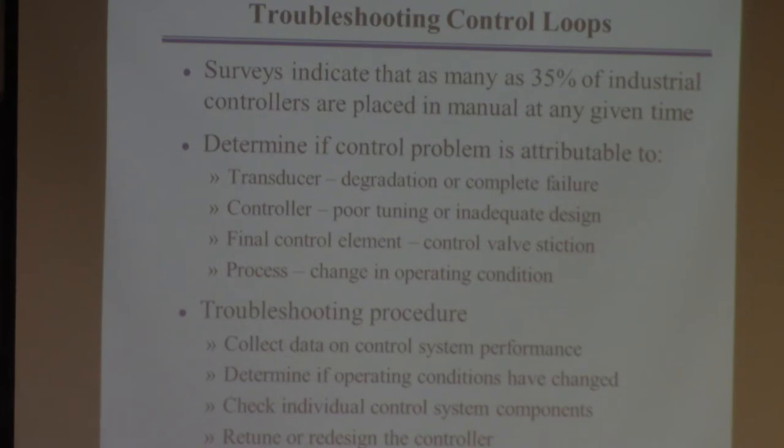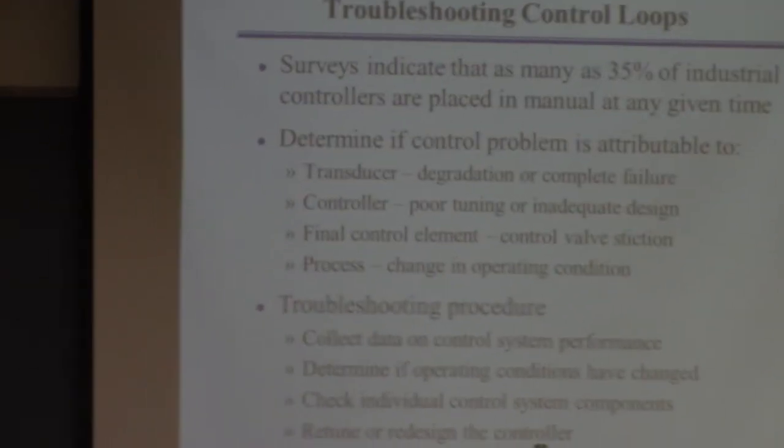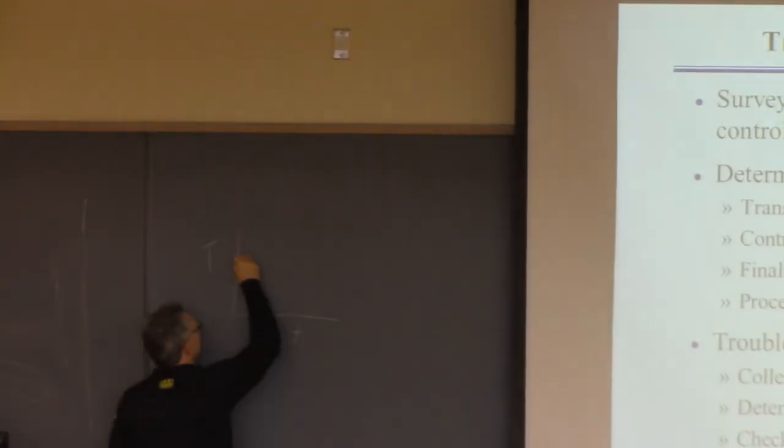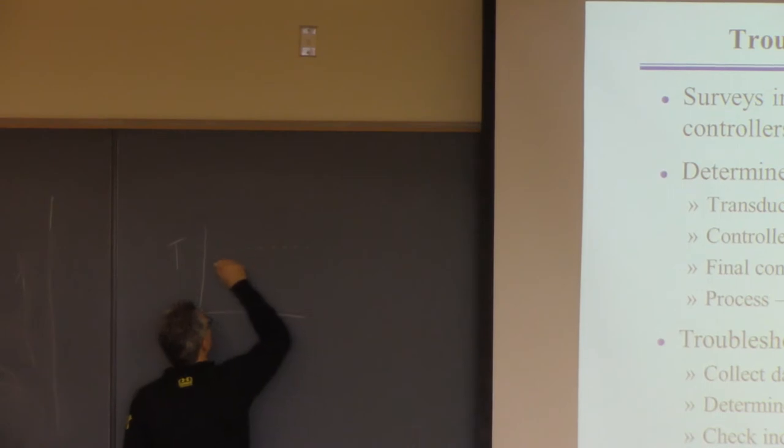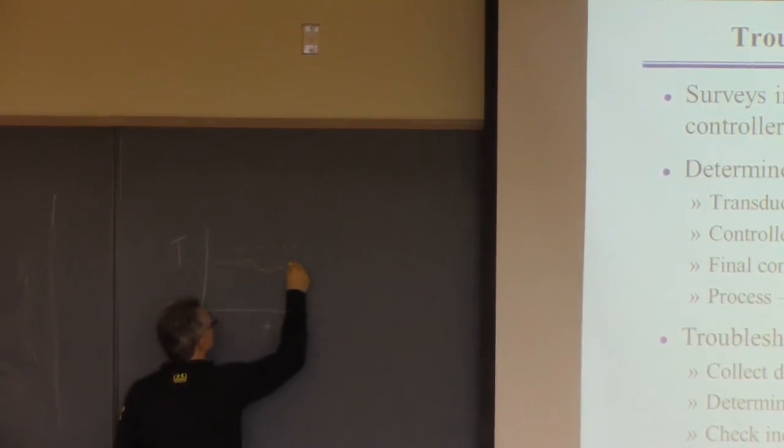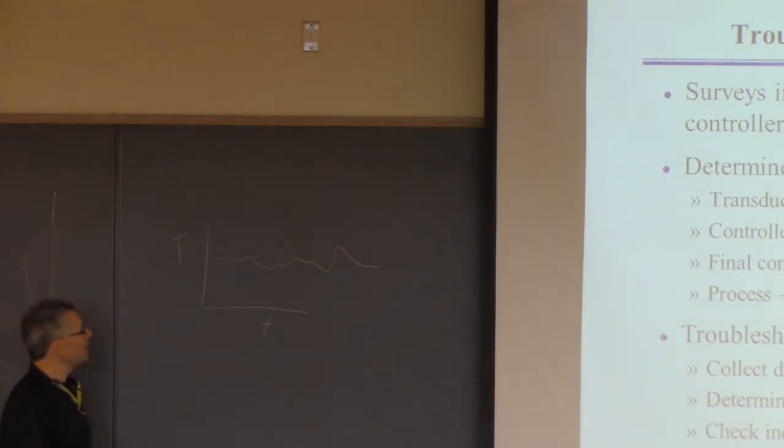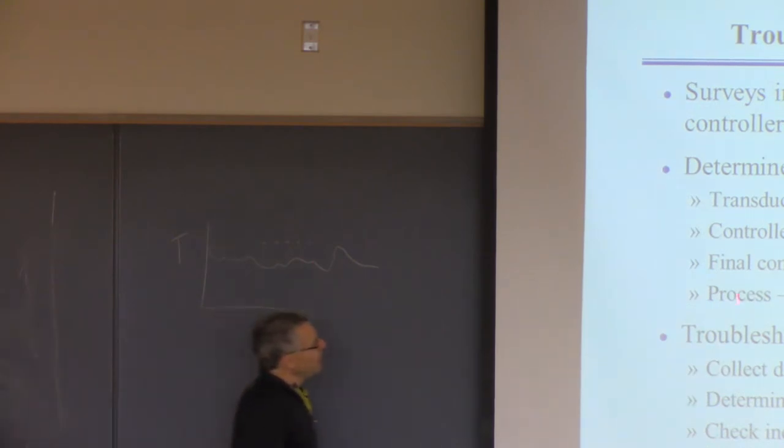So of course the problem is when the controller doesn't work, you don't know what the problem is typically. All you know the controller's not working. How do you know the controller's not working? Because here's the temperature, and here's time, and here's the set point, and here's the temperature. So if somebody sees this, either you or the operators, and they say hey, temperature controller on the heat exchanger E3 is not working. Then you look at it and you say, oh well, that doesn't look so good. So then the job is to figure out what's gone wrong and try to fix it.